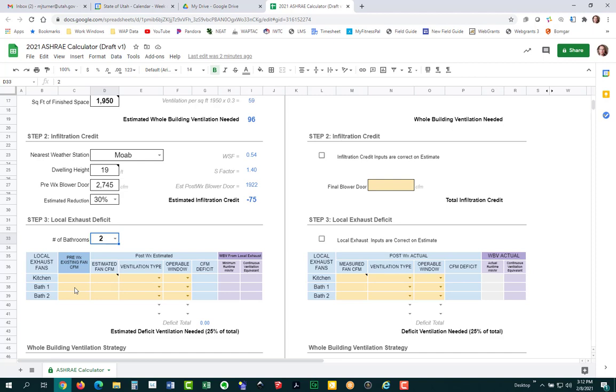In bathrooms, you're required to have 50 CFM of on-demand ventilation, or if the ventilation is going to be continuous — on all the time — then you only need 20 CFM. The idea is to move bulk moisture out of these rooms. The calculator does account for the 20 CFM continuous in bathrooms. The kitchen caveat is the one thing the calculator will not account for automatically, so be aware of that.